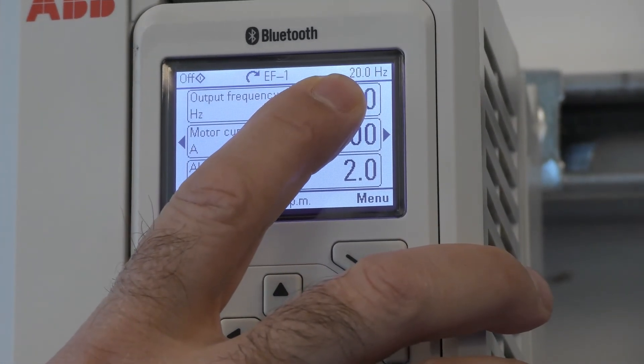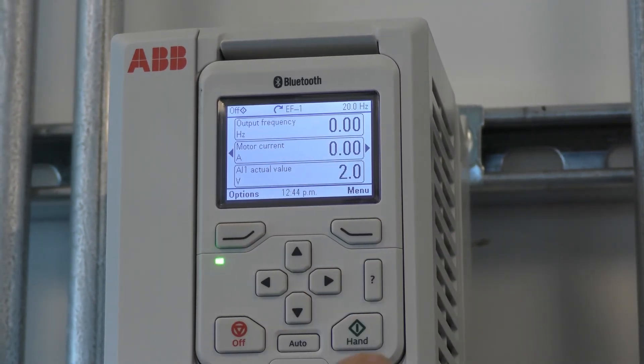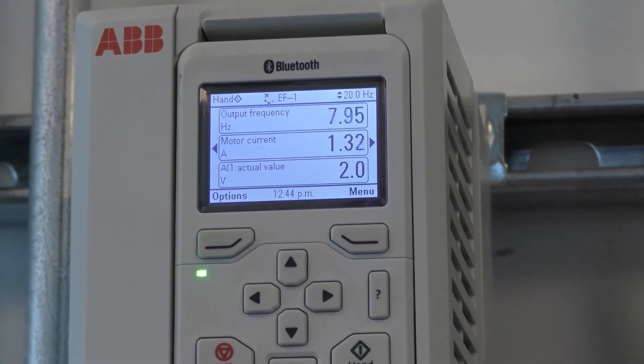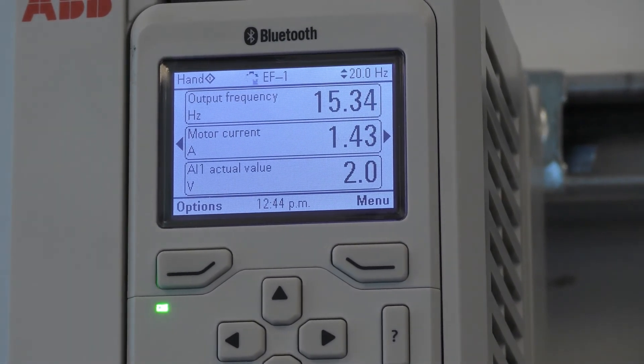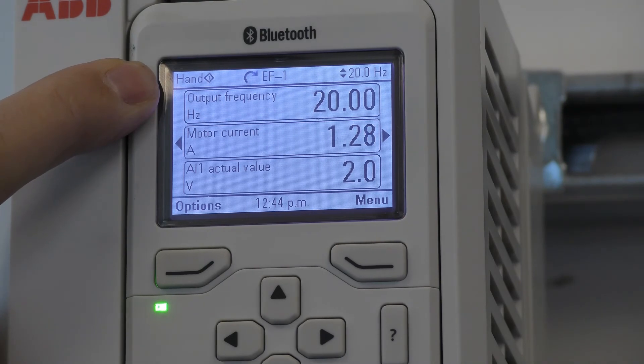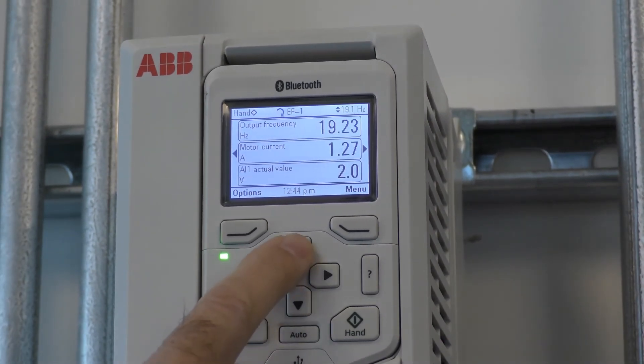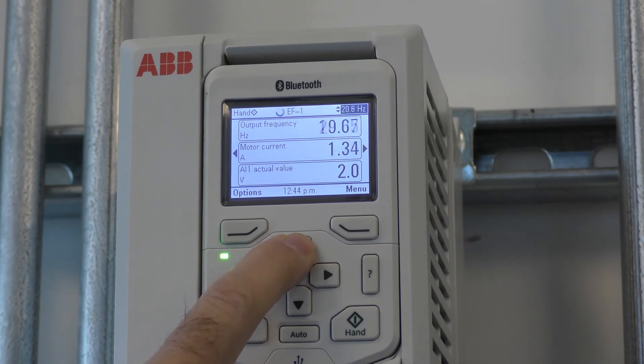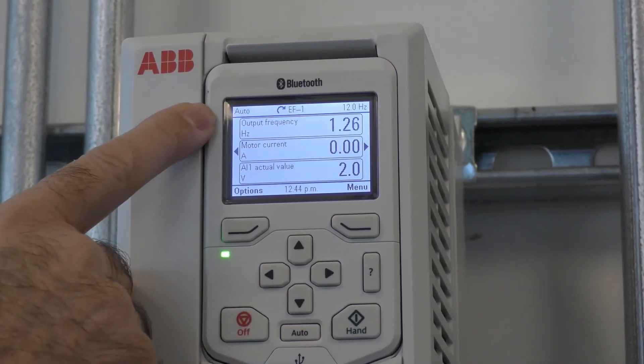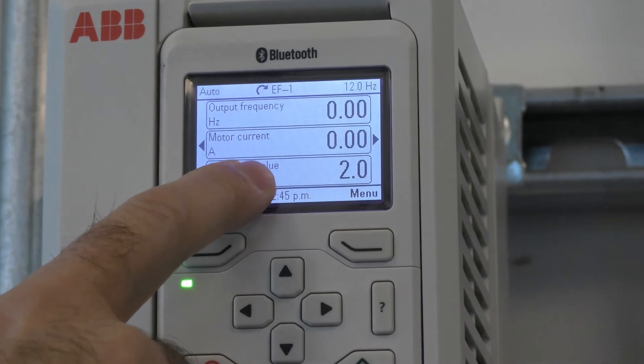This is the reference status — this was the last reference that was set on the keypad when it was in Hand mode. If I press Hand, it's going to go to 20 hertz. It'll indicate that it's in Hand, and I can use the down arrow to make it go slower and the up arrow to make it go faster. When I press the Auto button, it shows Auto and the reference signal is changed by this value. It's not running because there is no start.